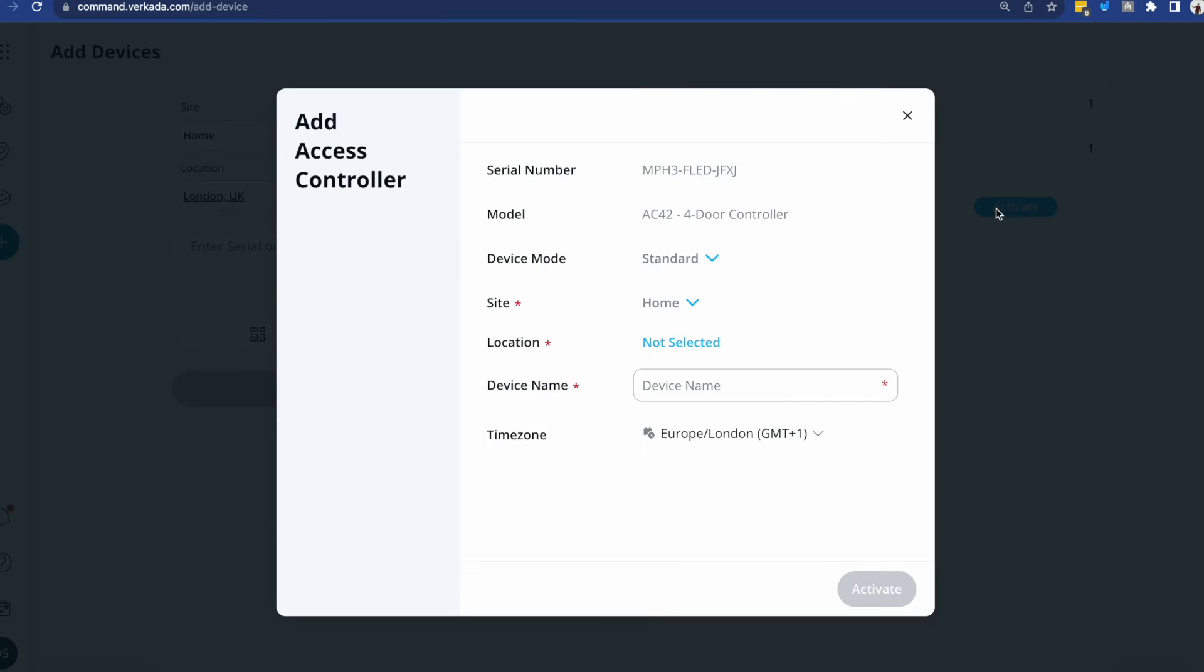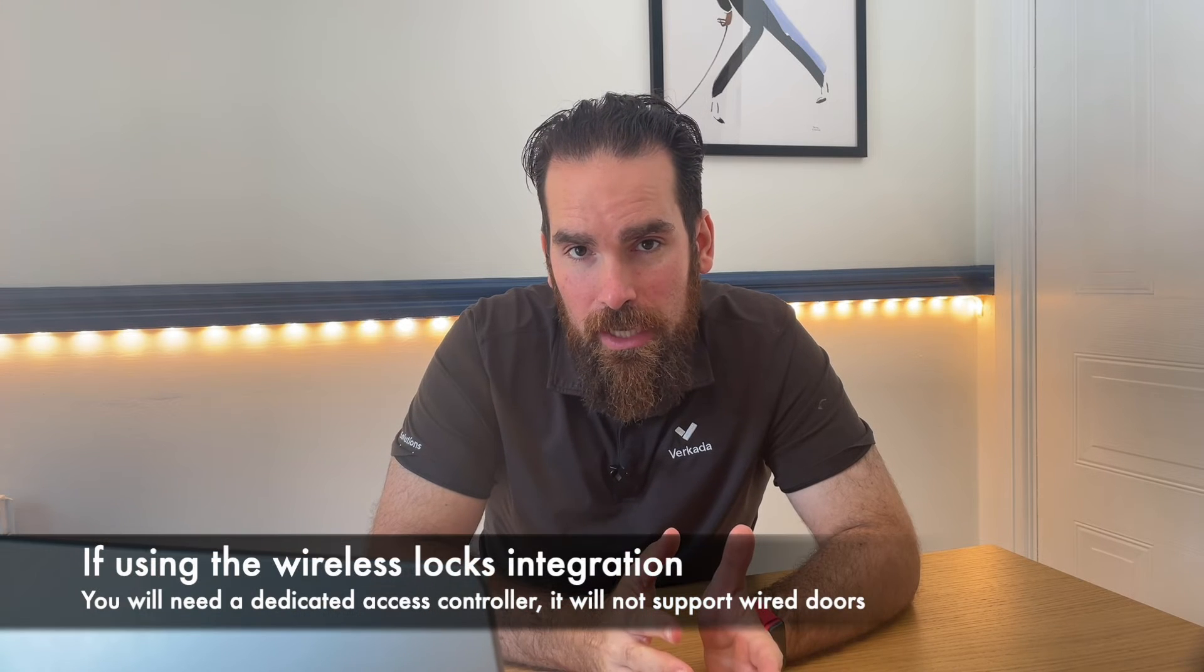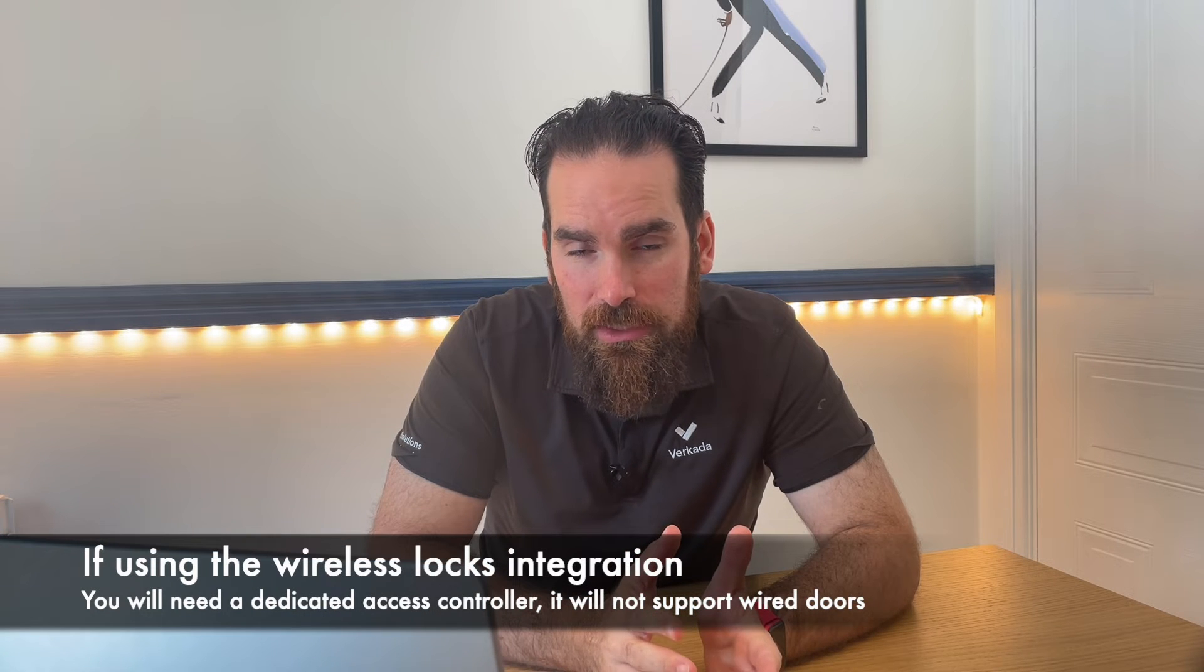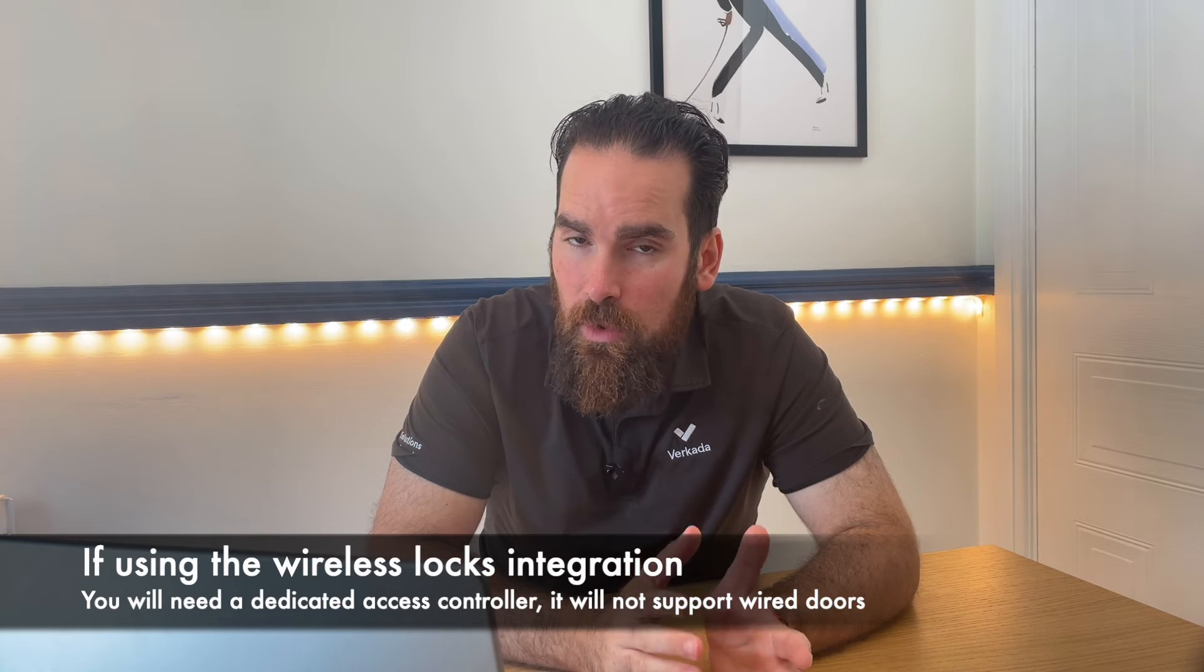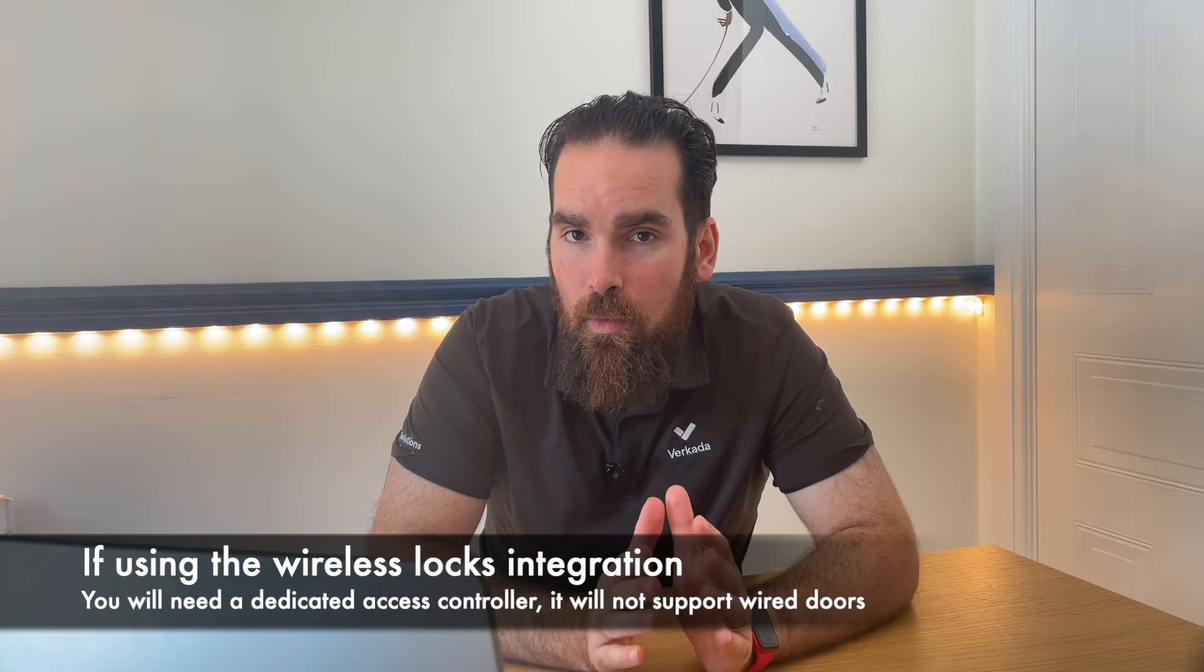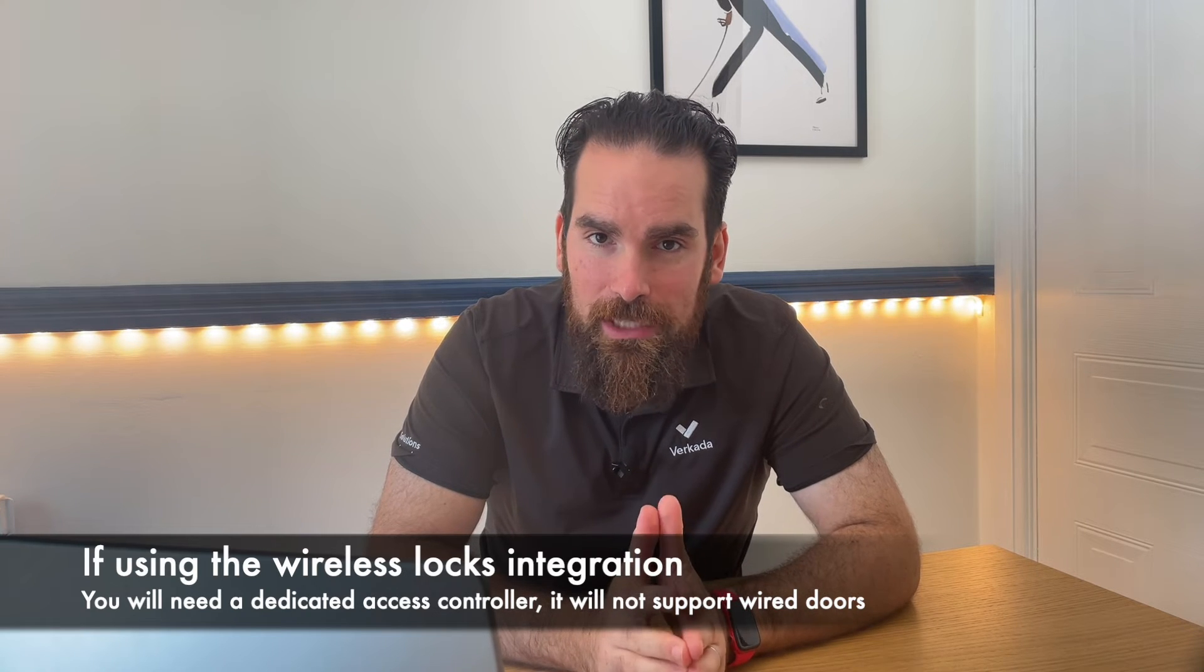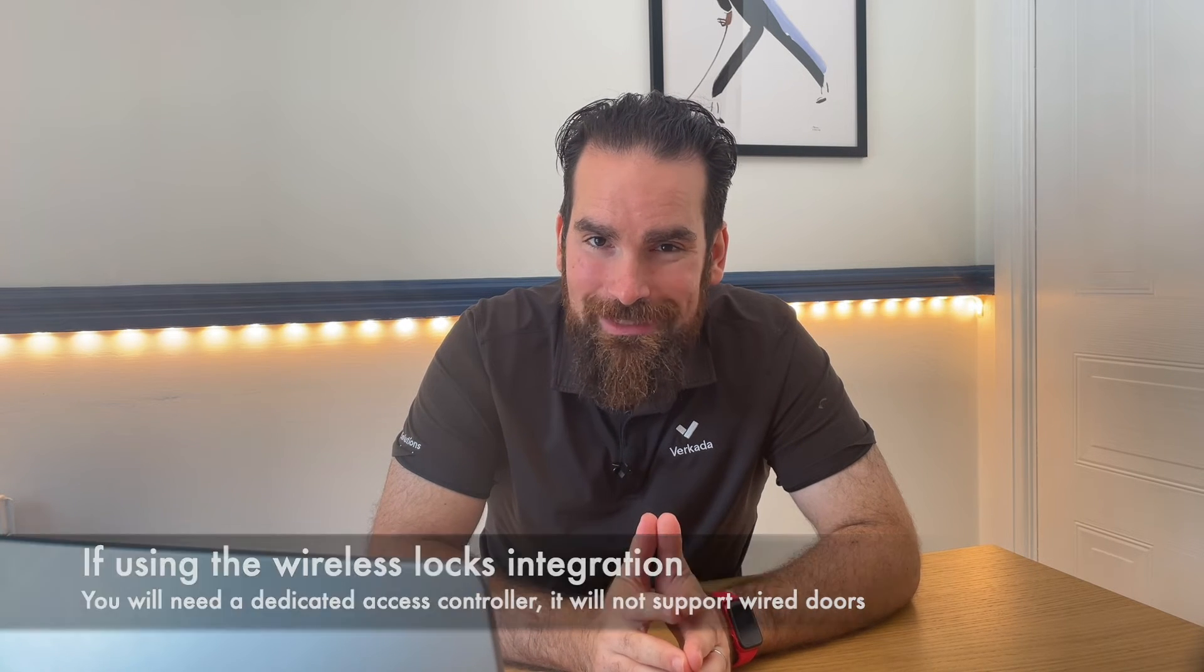Before the controller goes live, you get presented with a simple menu to allow you to either run it as a standard wired controller, or as a controller supporting Schlage or Assa Abloy Aperio wireless locks. At the moment of this video, a controller can either support wireless locks or wired locks, and there is no ability to run them side by side on the same hardware.